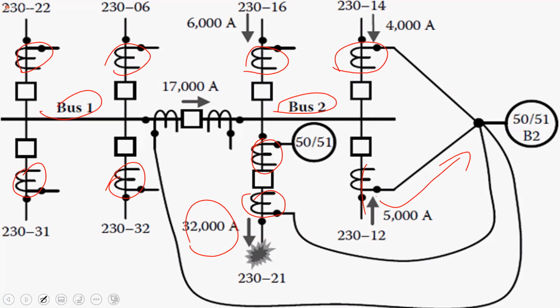Again, this CT, right? Obviously, well, I shouldn't say obviously, but there may be a fault on the system. You would note that you have 17, 6, 4, and 5. Those are all flowing into the bus bar, and we have 32 out. So based on what we see here, obviously we have a fault. Okay, so there's a fault on the system. The question is, how do the relays operate or behave in terms of clearing this fault?